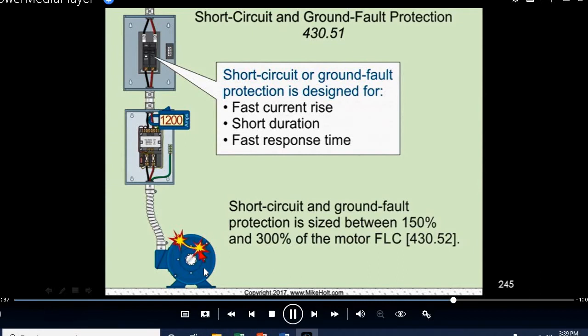And that protection is going to be sized between 150 and 300% of the motor full load current that's listed in the code book. This device right here is designed to protect against a fast rise current for a very short duration, and it responds very quickly. Where the heaters are designed to respond to a slow rise current, long duration, and a slow response time.